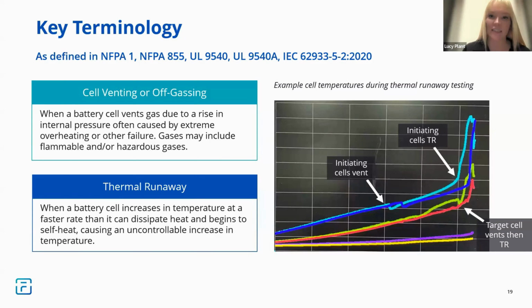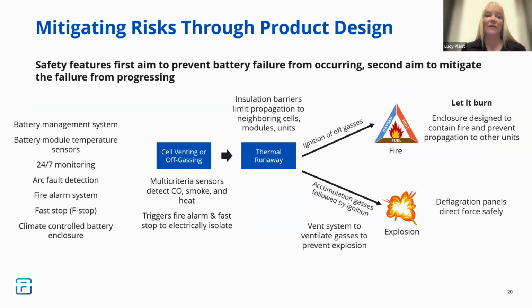If we go to the next slide. So, again, we talked about the stages of an event. Ideally, you would want to mitigate the event before it occurs. So if we see one of those battery cells running hot within our battery management system, we'll be able to pick that up. We want to isolate that cell and de-energize it so that it does not continue to be an issue. If we're not able to do that and the event continues to progress, the first step will be off-gassing. Again, we're going to have multiple detectors within the system itself to be able to detect when this event is occurring so that we can monitor it.